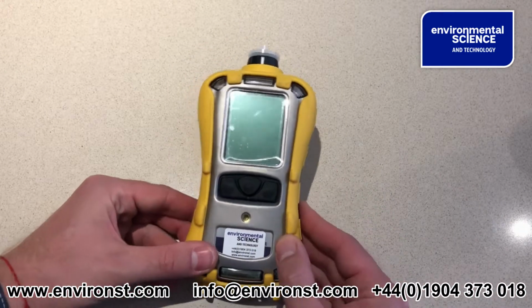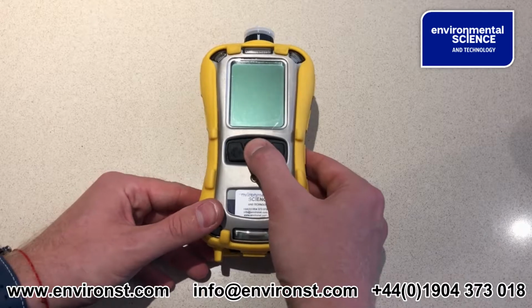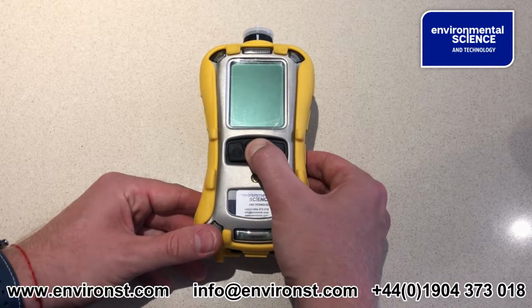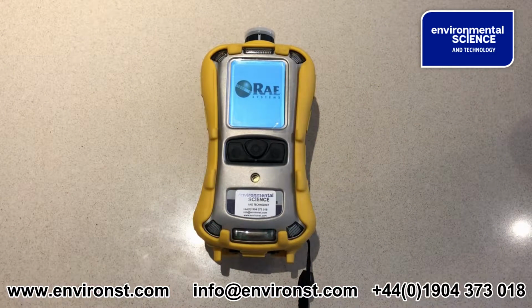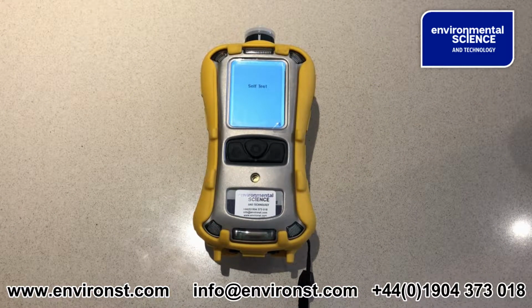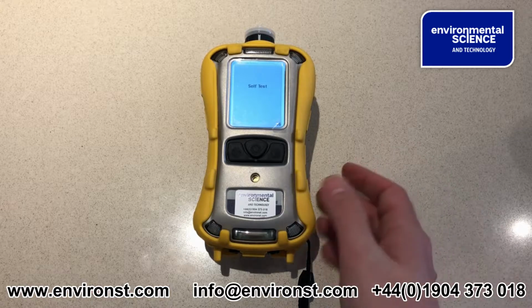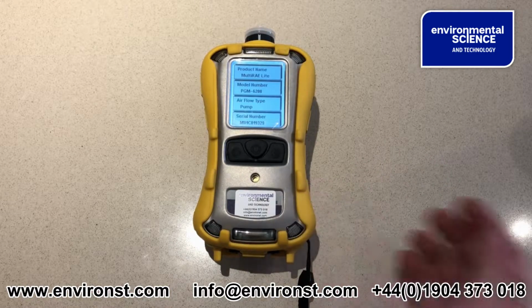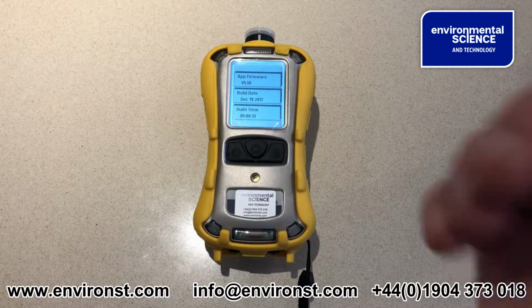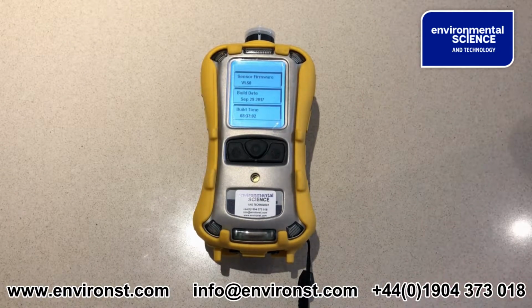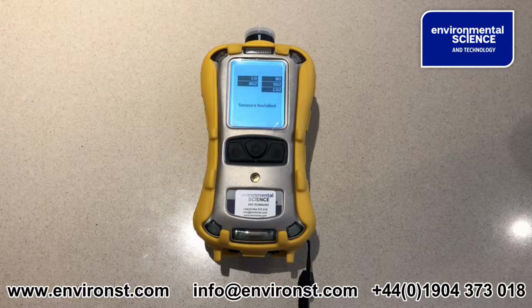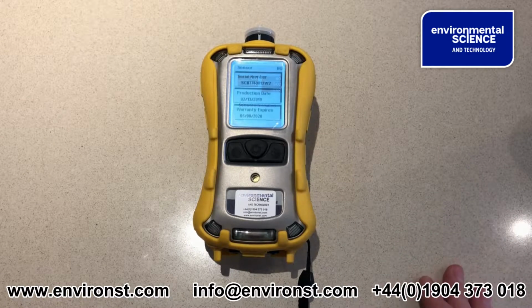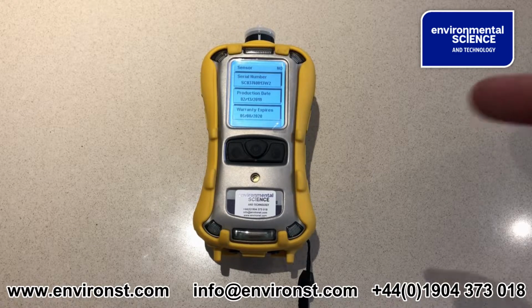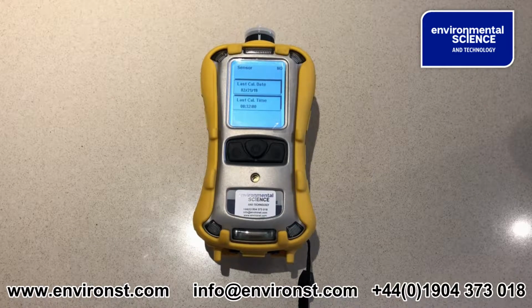To turn the unit on, we press and hold the power button. The unit will give you an audible warning that it's started up, and it will go through its self-test and startup mode. Whilst it's doing this, it will tell you the firmware revisions and the sensor firmware revisions, its configuration, and then it will go through each individual sensor, telling you its last calibration, when it was originally manufactured, and its current alarm values.